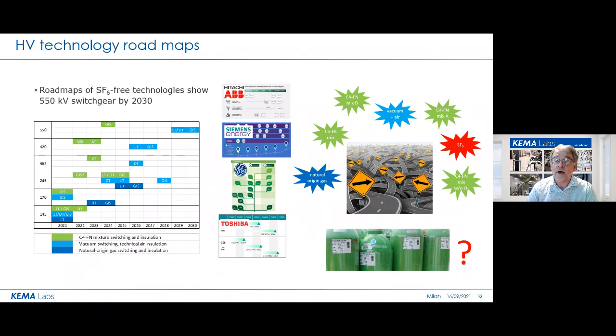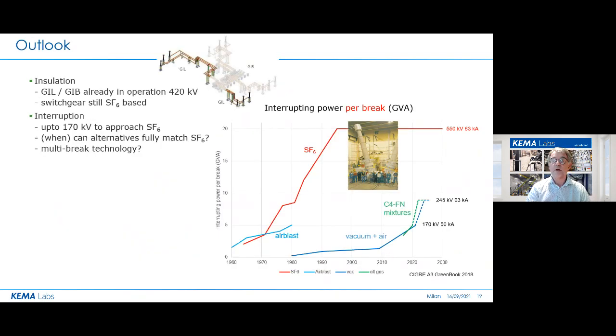Let's have a more concrete look at projects that are involved here. The insulation capability of SF6-free gases is under demonstration right now. A 420 kV GIL has been in operation a few years already with F-gases mixed with CO2 or N2 as a buffer gas. Natural origin gas insulated bus ducts have been announced. A number of SF6-free 420 kV substations are in development. In those cases, in the first phase, SF6 breakers will be inserted in the SF6-free GIS, whereas in a later phase, adequate SF6-free breakers will be inserted when these become available.